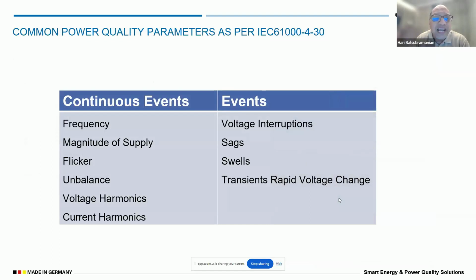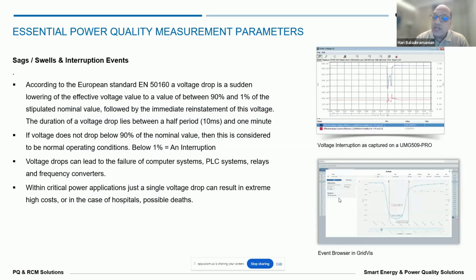So I can classify these power quality parameters into frequency, magnitude of supply, flicker, unbalance, voltage harmonics, and current harmonics. And then there are events which happen once in a while: voltage interruptions, sags, swells, and transients. We will see some of these points here. Let us see sags and swells, which are very common. A sag is a very short-term voltage drop below 90%, and a swell is a voltage rise above 110% of the nominal voltage. These are given as per standards, and we will also see those standards, EN 50160 and IS 17036, which I think is the equivalent of EN 50160 in India.